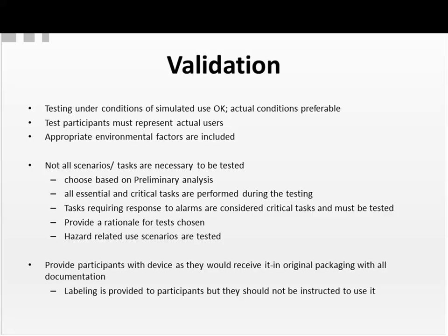Now, at the beginning of the validation, you give the participants the device as they would receive it in real life, in its original packaging, with all the documentation, labeling, the manuals. As far as labeling goes, it's given to the participants, but they are not instructed to use it. They use it if they feel they want to use it.